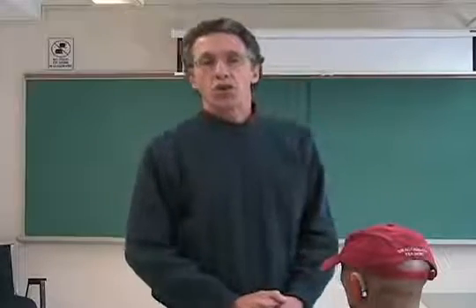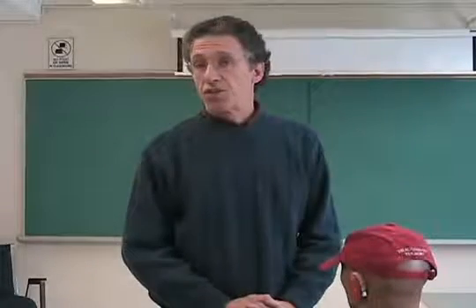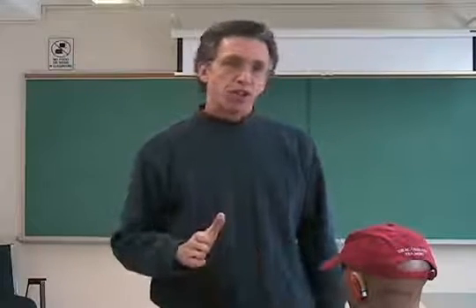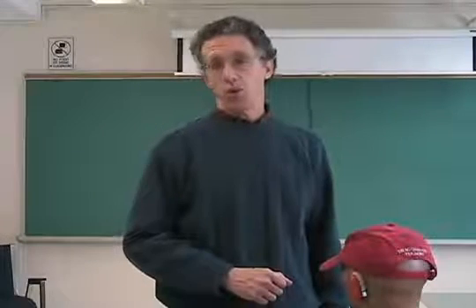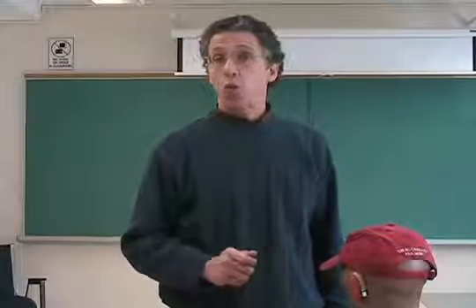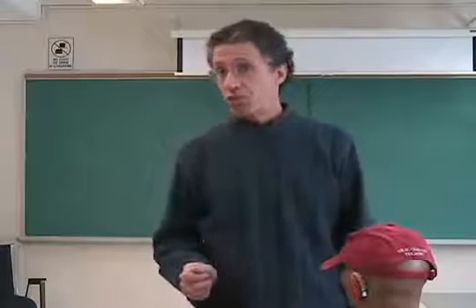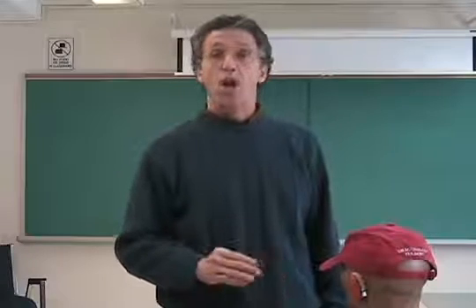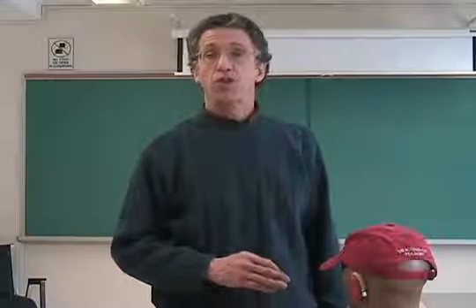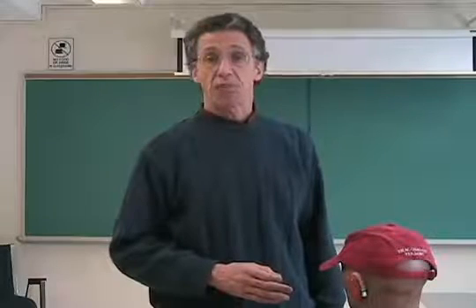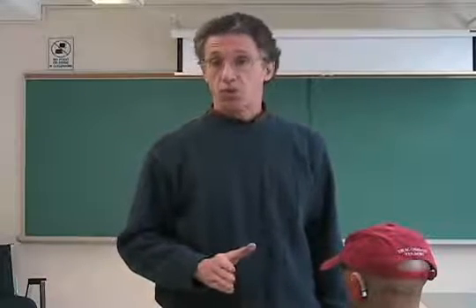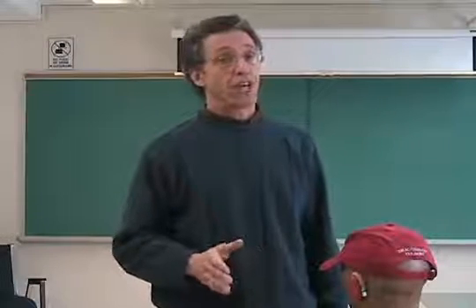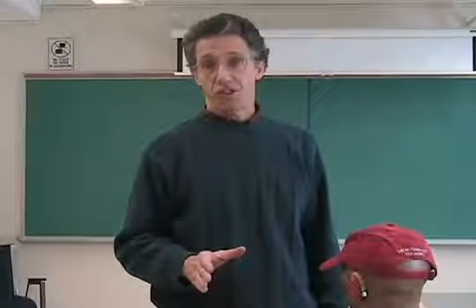What we would now like to show you is what happens when noise is added to the factor of listening through a hearing aid. To demonstrate the interaction between distance and noise, we will use the following noise sources: a teacher working in the back of the room with some students. This will simulate what could happen in the regular classroom. We will also turn on a fan to simulate the noisy blower fans that many classrooms have. As the noise sources start, I will again walk ten feet away from the hearing aid, and you should notice that we have an extremely difficult listening condition.